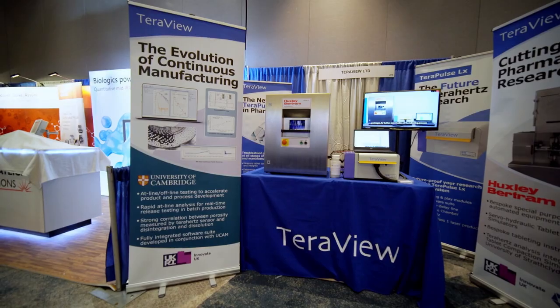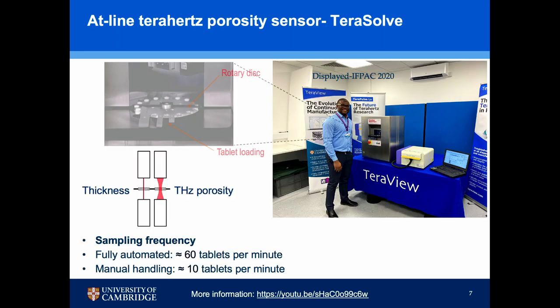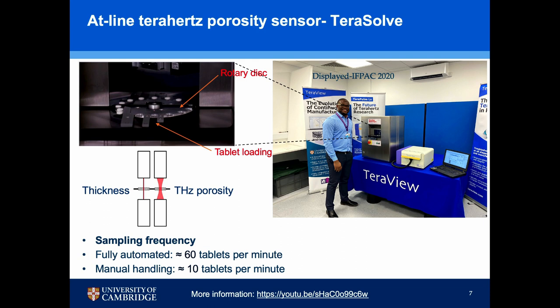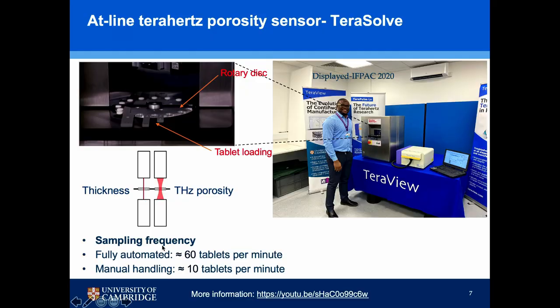This is the at-line sensor, which was displayed during last year's IFPAC meeting. The at-line sensor is basically composed of a rotary disc. We load the tablet onto the disc, which rotates and positions the tablet in front of a laser gauge that accurately measures the thickness. From there, it positions the tablet in front of the Terahertz pulse and the porosity is measured. When fully automated, we are expecting about 60 tablets per minute to be measured. Currently, we are doing manual feeding, so we are able to measure about 10 tablets per minute.